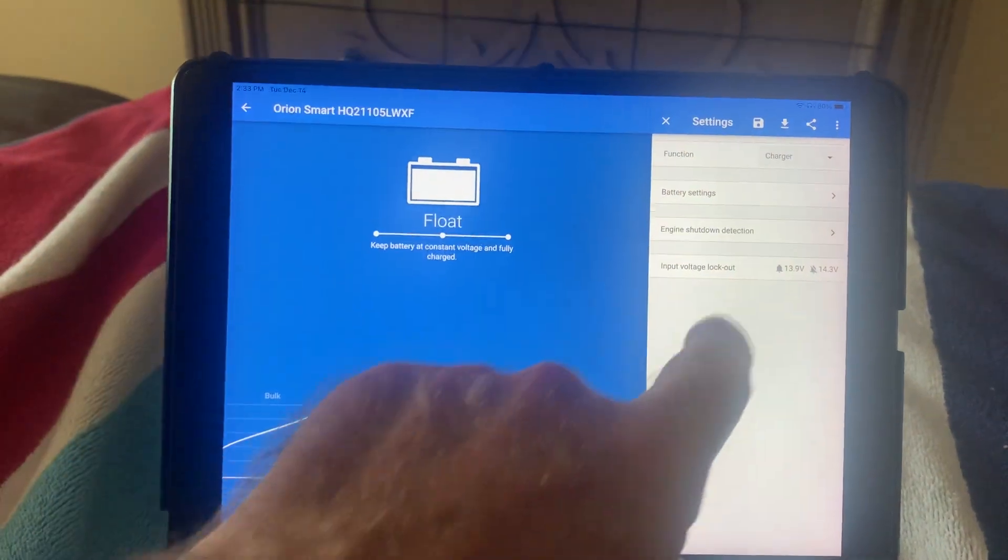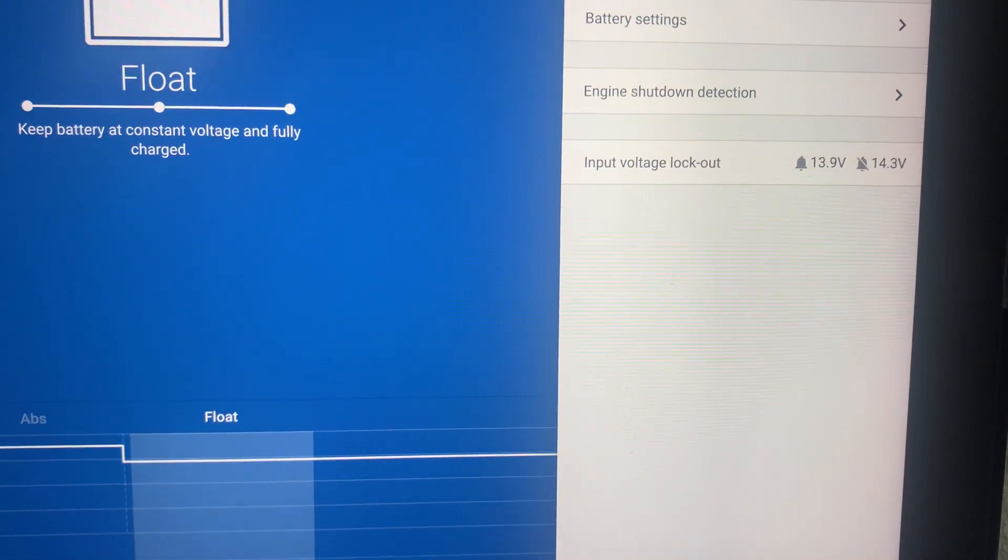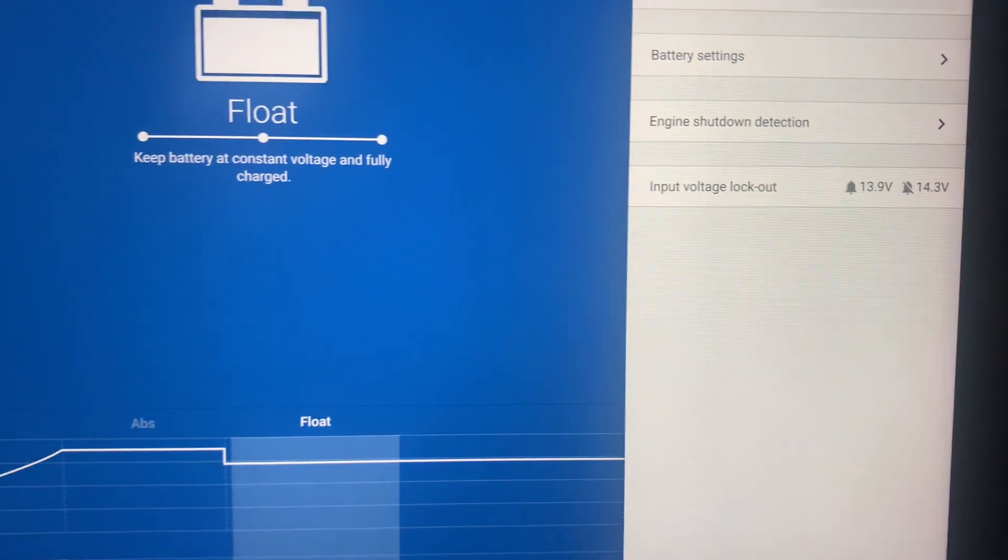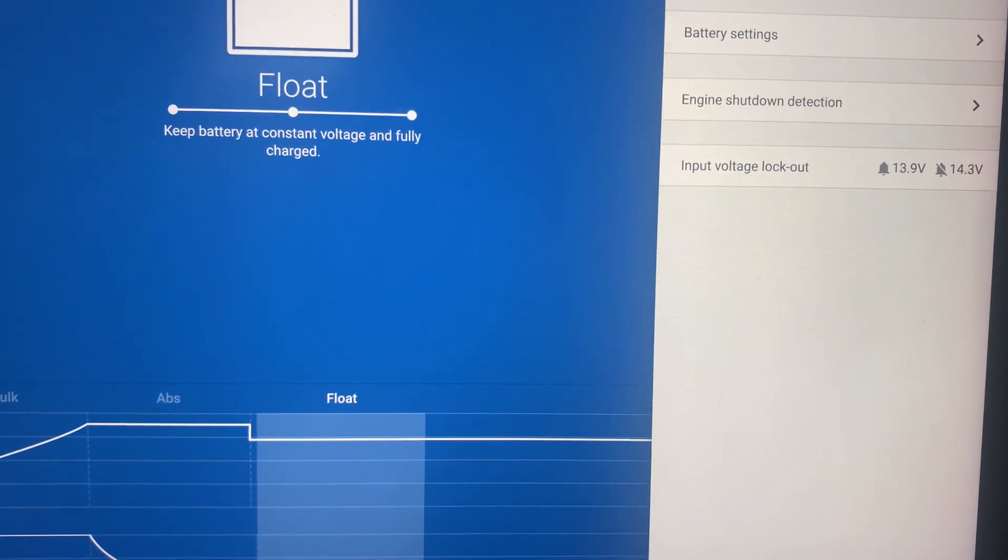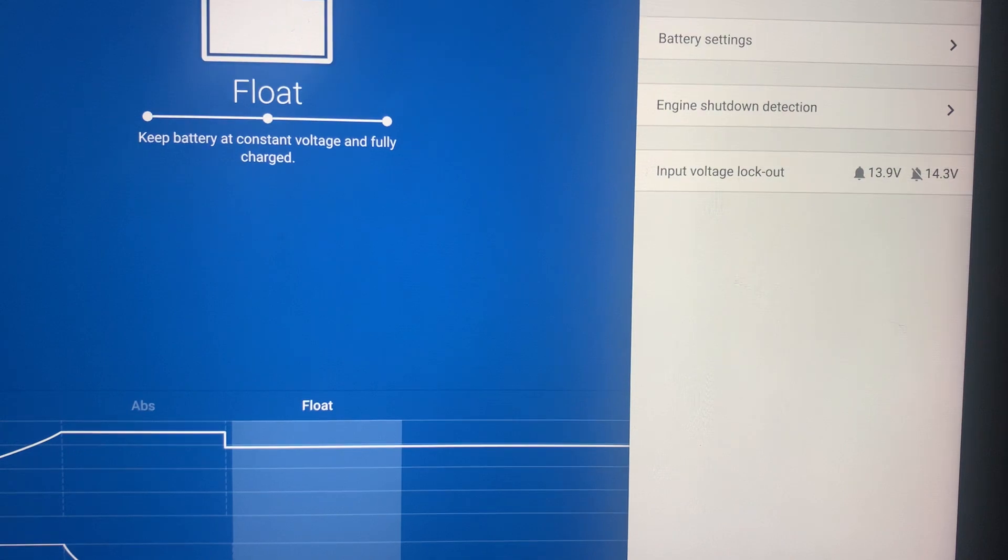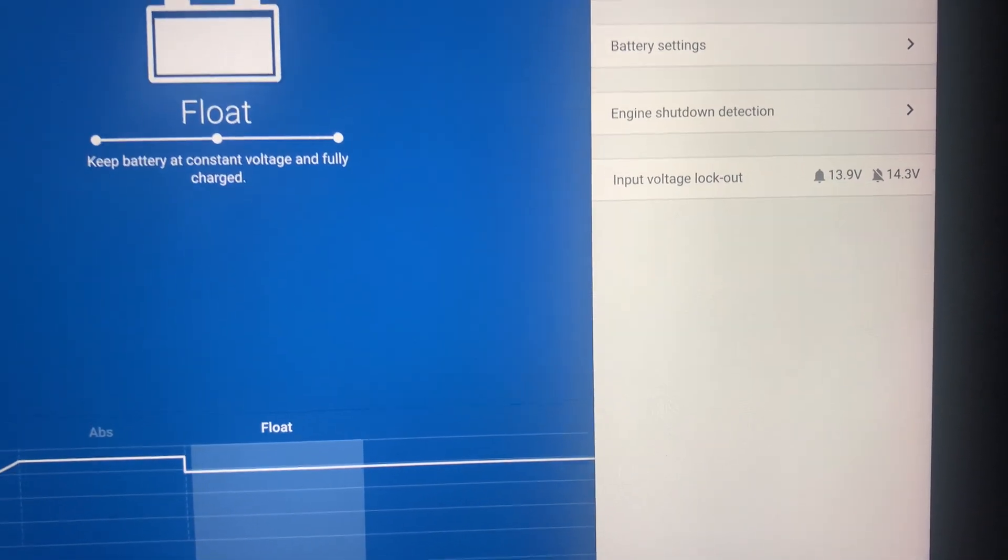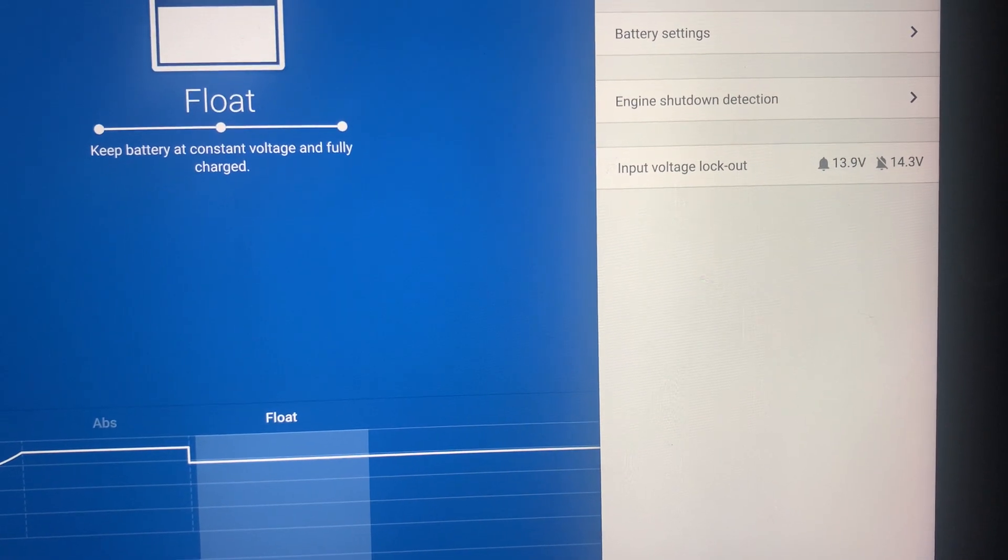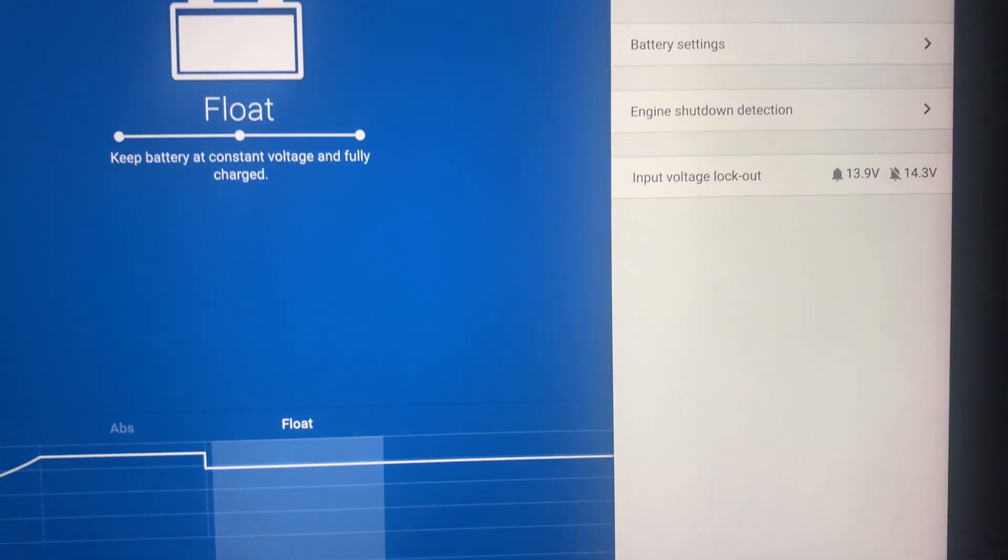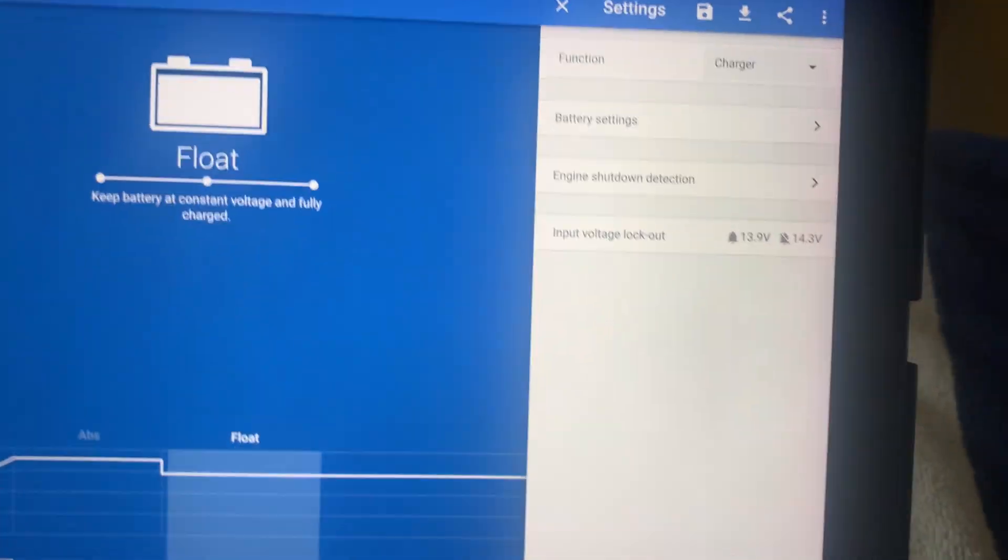I've told it not to come on unless the main battery is at 14.3 volts and 13.9 would be your lockout. So as soon as it sees that the battery has hit 14.3, which for me is right at the absorption float phase, then you can go ahead and consider charging this guy. But if you drop the main battery voltage down below 13.9, then I want you to stop and just let it be.